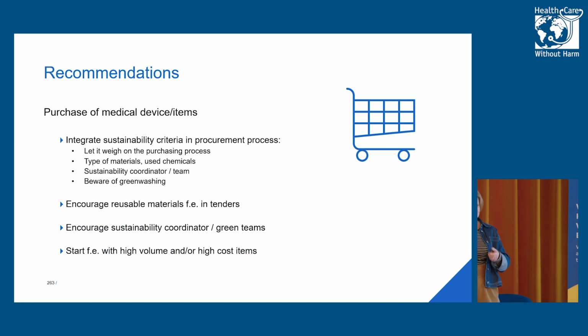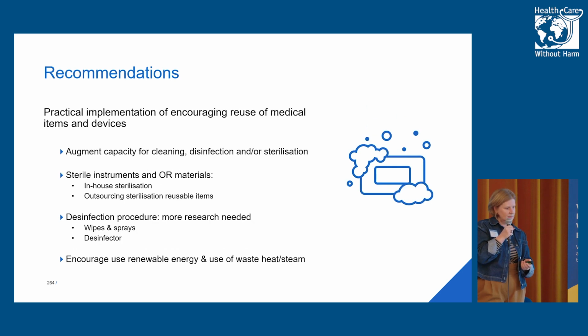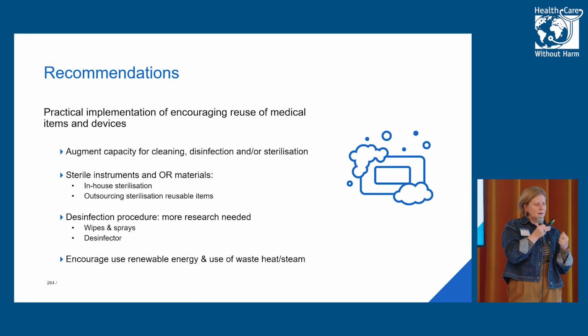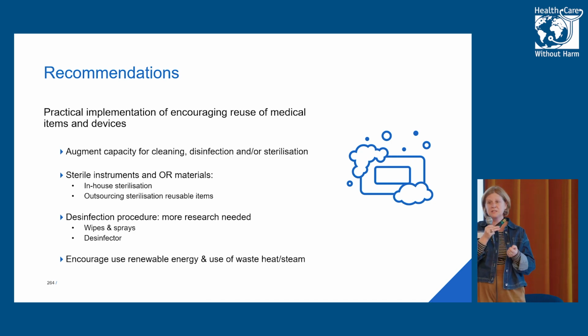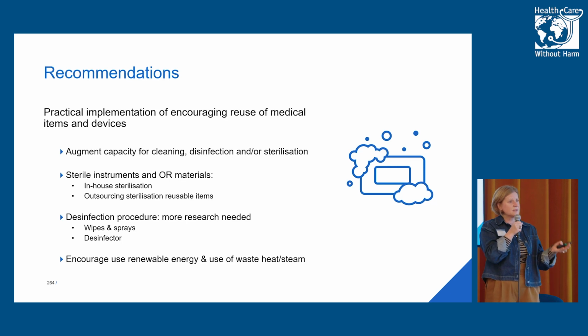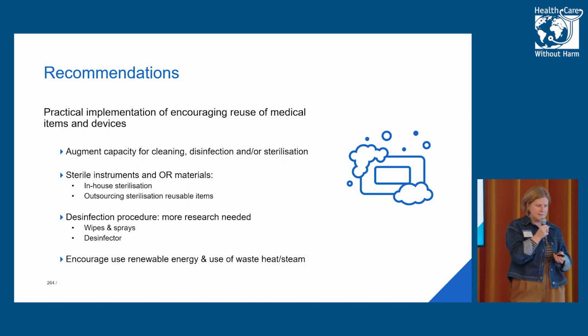Reusable items should be encouraged to be included in the procurement, because often tenders are only for single-use items and the reusables are often not considered. Also, when you implement in the hospital to encourage reuse of the medical items, you have to be aware to augment the capacity for cleaning, for disinfection, and for sterilization. That requires a good process in the hospital. For sterilization, for instance, you can do it in-house if you have enough capacity, but there are also possibilities to outsource the sterilization of instruments.